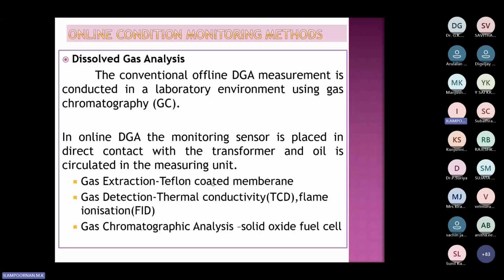You put in a membrane, and depending upon the pressure level variation, you will have the gas extraction. That can be detected with a thermal conductivity detector or a flame ionization detector. Both work on different concepts actually, so there will be slight changes. And of course, after that, you have to put it in the solid oxide fuel cell, through which you will have peaks varying depending upon the gas concentration. And from that, you can identify the ppm level of the gas in the oil.